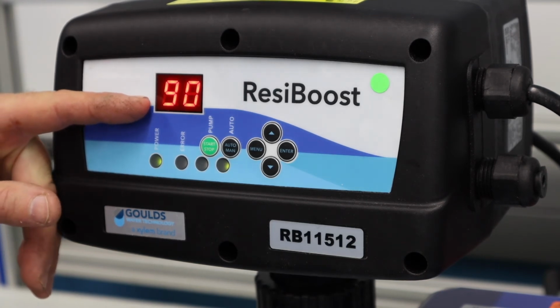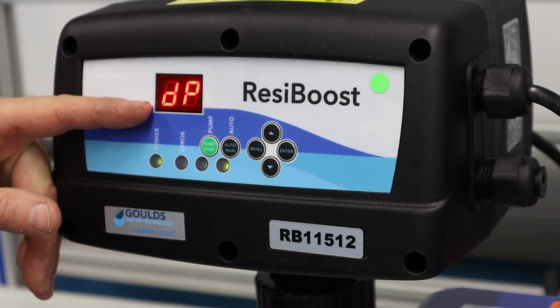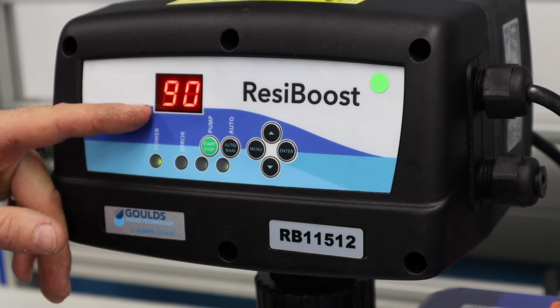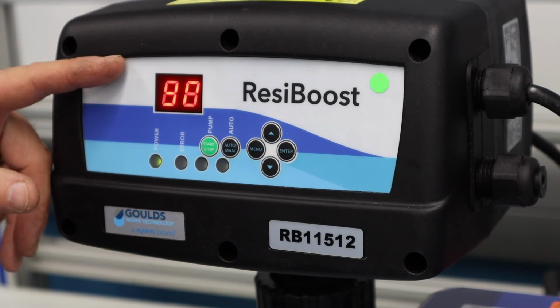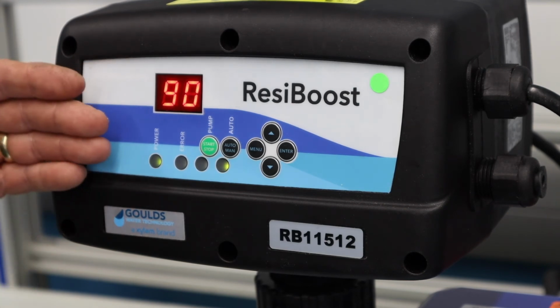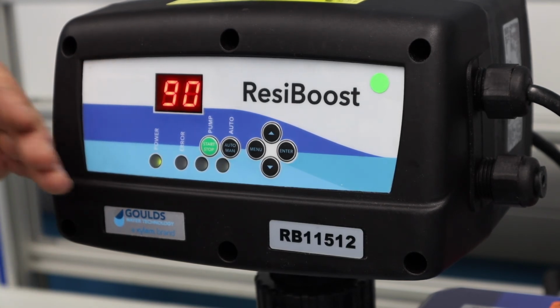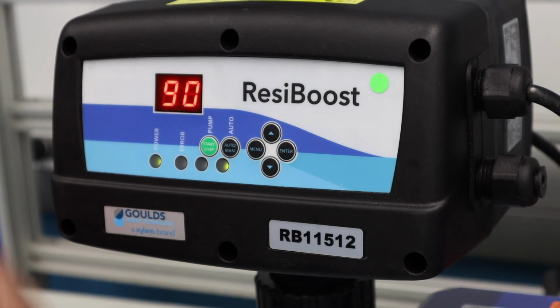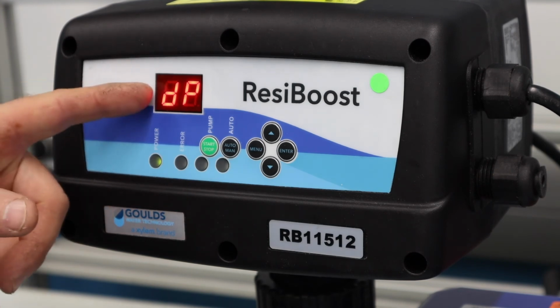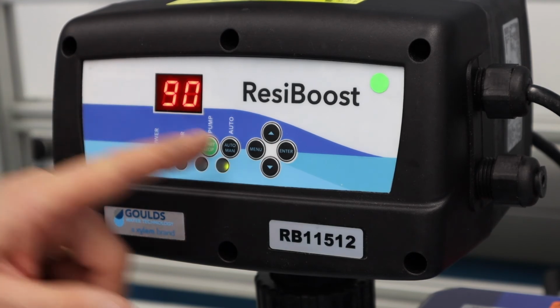The next is DP, or pressure drop. When do you want this thing to wake back up again? And we can see this is a percentage. And so the default is 90% of your set point. So we got to do a little math. 90% of 60 is 54. So it's going to go down, it's going to start at 54. So that's your start point. So that's always a percentage of the set point.